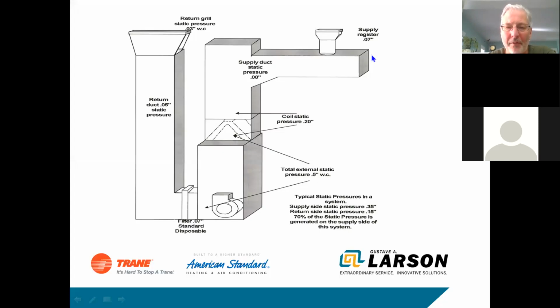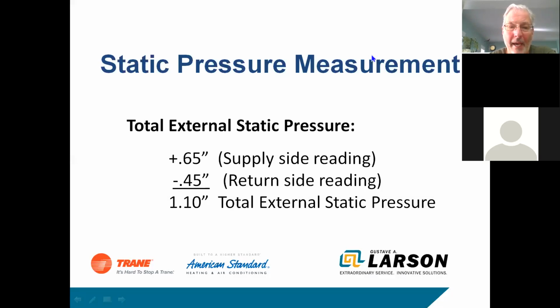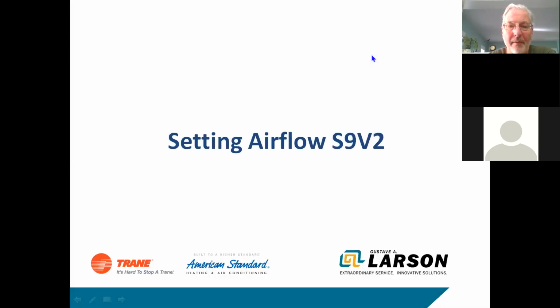Static pressure measurement, again, it needs to be between the filter and the blower for the return. It needs to be between the A coil and the heat exchanger for the supply. Add them together, and that's your total external static. And I know I'm going through this kind of quick, but we're a little pressed for time.